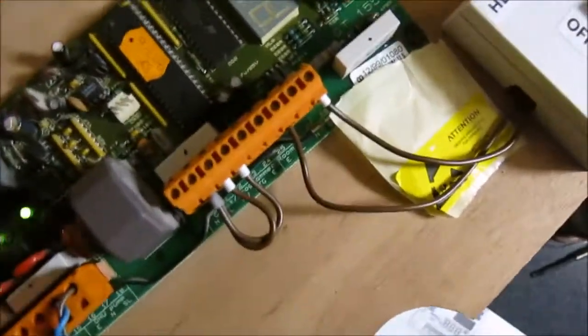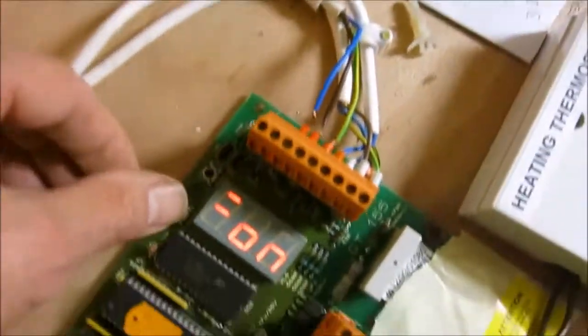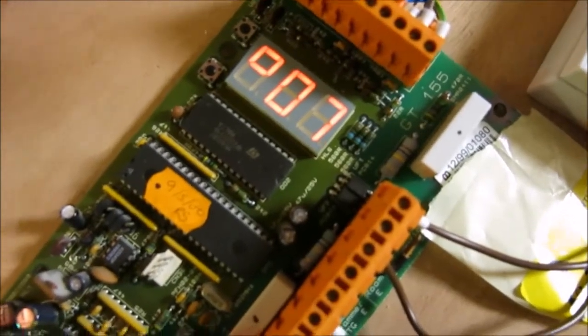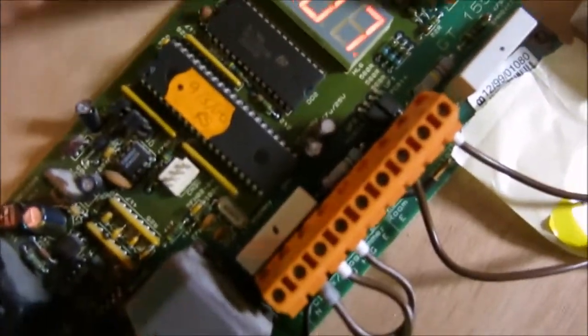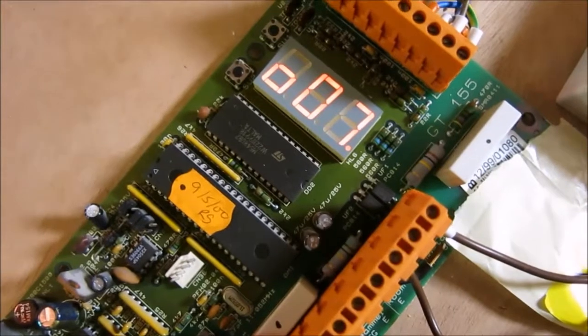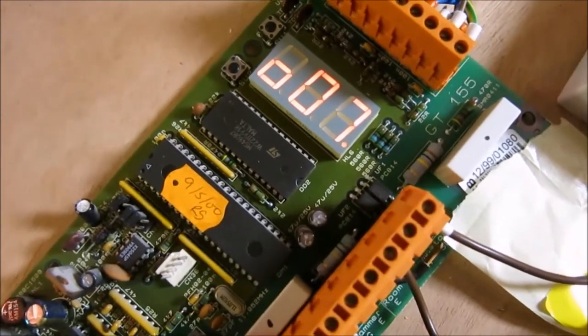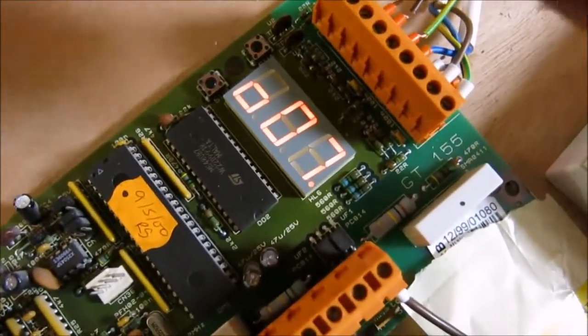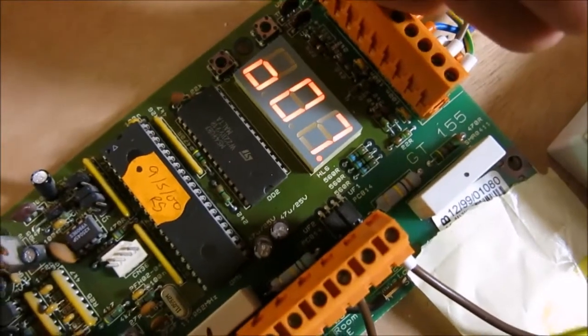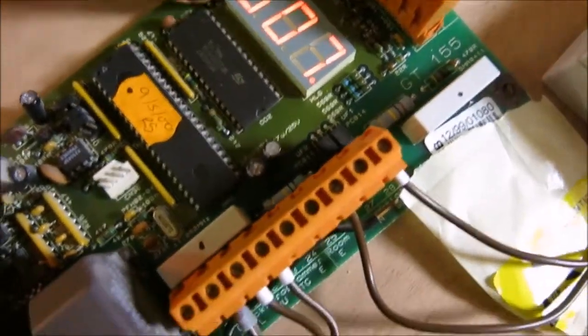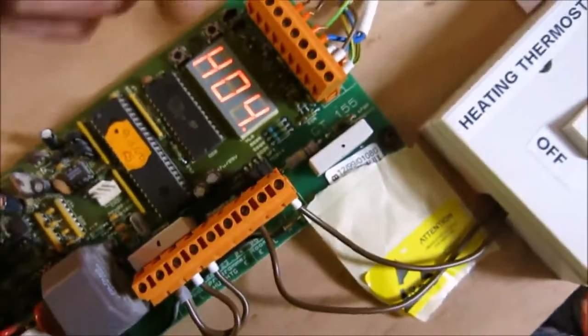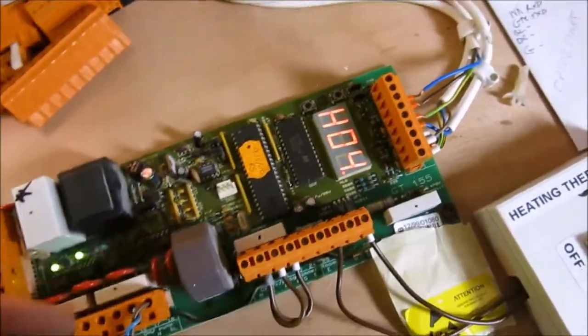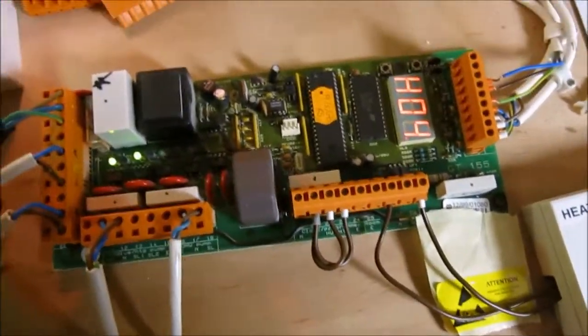If, say, you turn this on and you did SW2 and the heat store was showing 65 degrees and then one of the others is showing something like 88, then clearly that can't be right and there's something wrong. Or if, say, the heat store is showing something like 99 degrees or something daft like that, then those readings are wrong and there's something wrong with one of the thermistors. So that's a little bit of information on that.